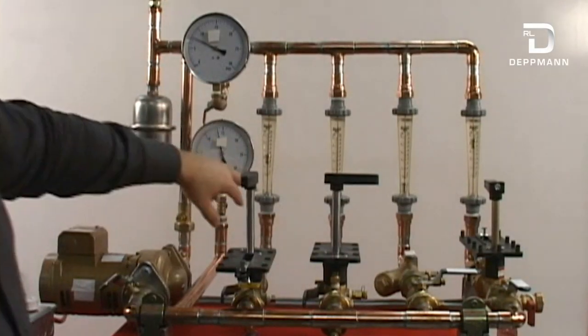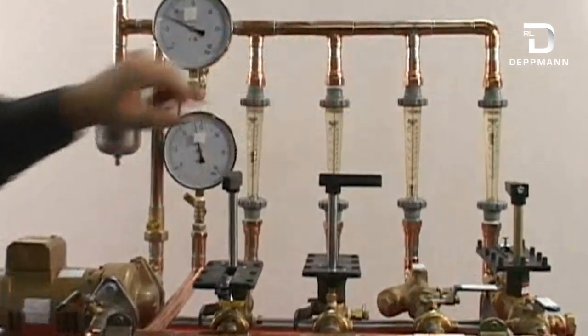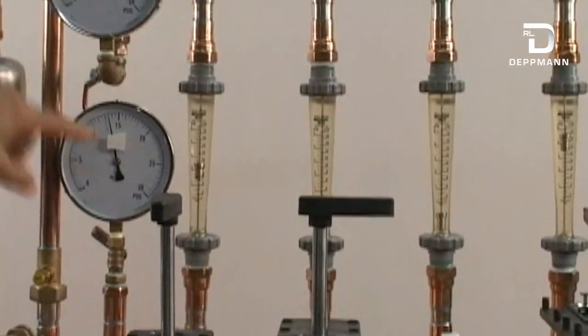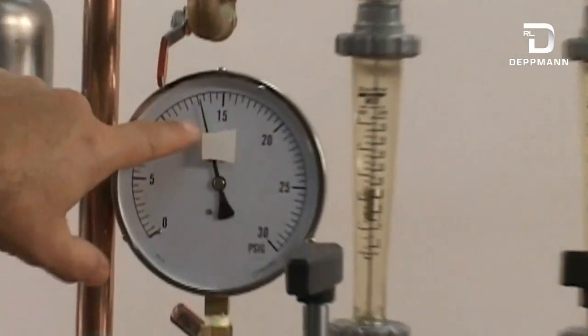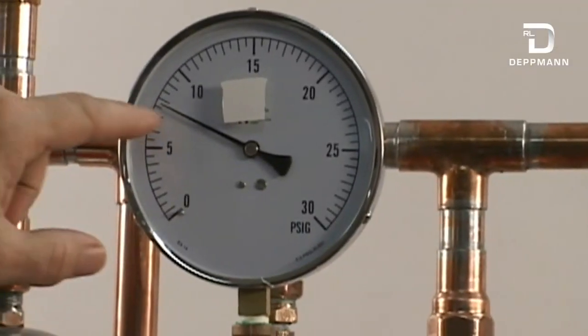Our system's up and running. We've got flow through this zone and this zone, and you see our differential pressure. Roughly we're at 14 pounds right here and roughly 8 pounds here.